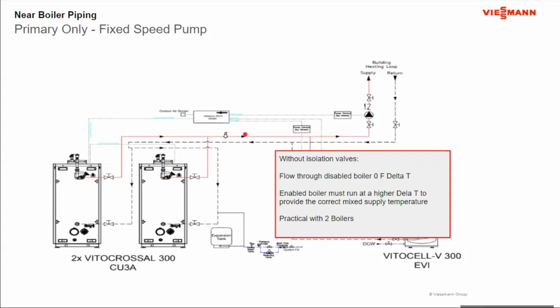Now my control normally will have a common supply sensor down here. Because of that common supply sensor driving the temperature, and because half of the flow is not being heated, the on-service boiler is going to have to run at twice the delta T to provide the right water temperature. So if the system was running a 20-degree delta T across that boiler, I'd probably have a 40-degree delta T to maintain the proper temperature out of the system.